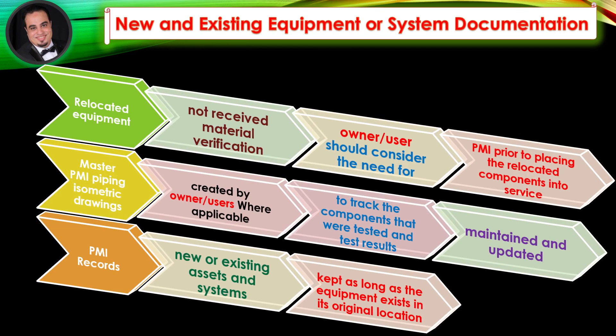For new and existing equipment or system documentation, and for relocated equipment with not-yet-received material verification, the owner-user should consider the need for PMI prior to placing the relocated components into service. Master PMI piping isometric drawings are created by owner-users where applicable to track the components that were tested and test results, and should be maintained and updated.